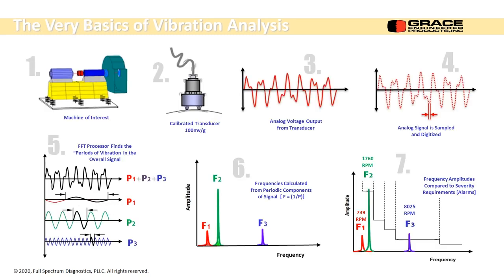Okay, the overview, the very basics, we have the machine of interest. So we're going to choose a machine, and knowing the machine is important when you're setting up your database, because each machine has a different allowable vibration level based on its design. Okay, they're not all the same. We're going to put our transducer on it. This is a calibrated transducer. You see something like 100 millivolts per G. That's typical. That will give us a value that means something.